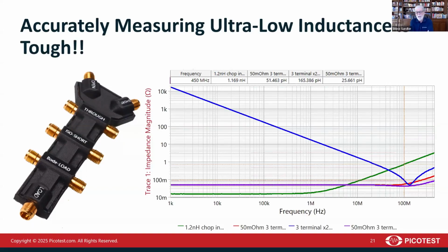One is that if you're like me using the Bode 500 for my measurements, that doesn't have the most intricate calibration support capabilities. In fact, it doesn't support calibration kits, but we would still need to be able to not only calibrate the instrument, but fully de-embed the mount. And so that became one of our challenges this year, was to make a calibrator that was ideal enough to measure these picohenry uncertainties.